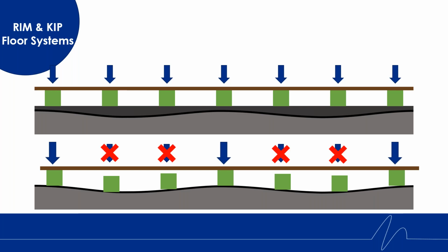This will lead to greater loads being imposed on fewer isolators. In the first example, we are able to determine the deflection of the system. In the second example, it is nearly impossible to determine the deflection of the system since some of the isolators are not properly engaged.